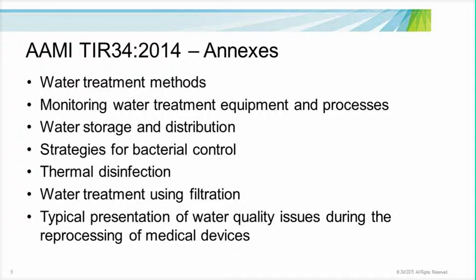The Water Treatment Using Filtration Annex goes into detail on the pretreatment filters, which remove debris and organic material, and submicron filters, which remove organisms. The last annex covers typical water quality issues that may be found during the reprocessing of medical devices. This part is brand new to this document and has great pictures of observed problems, causes, and recommendations. It's really a great flow chart that shows exactly what to do with different problems associated.